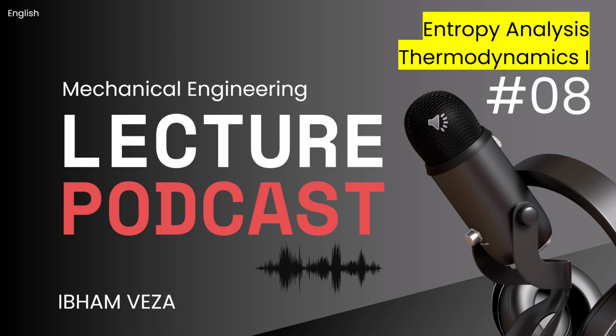Right. So, if we want to minimize that work input, put the least energy into a compressor, what are the actual strategies engineers use beyond just aiming for that perfect reversible ideal? Well, the most practical way, really, is to actively keep the specific volume of the gas as low as you can while you're compressing it. Okay, keep the volume low during compression. And since specific volume is directly tied to temperature. Right. So you need to keep the gas cool. Exactly. Keep it as cool as possible during the compression process. That's the key practical lever.